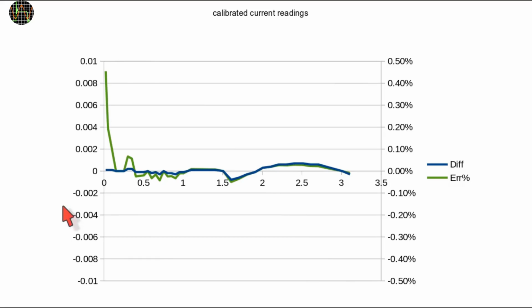The results in graphical format. With the calibration, the INA219 and the reference instrument track very closely, as you can see. The difference stays very close to zero over the whole 4 ranges. The error is under 0.1%, which is excellent. We already discussed the apparent rise on the left is a mathematical artifact of the way the error is calculated.